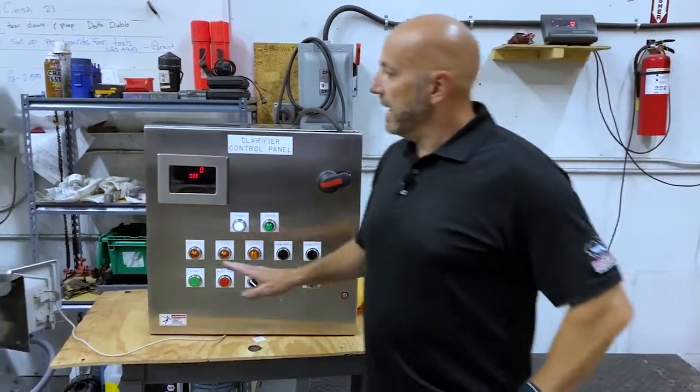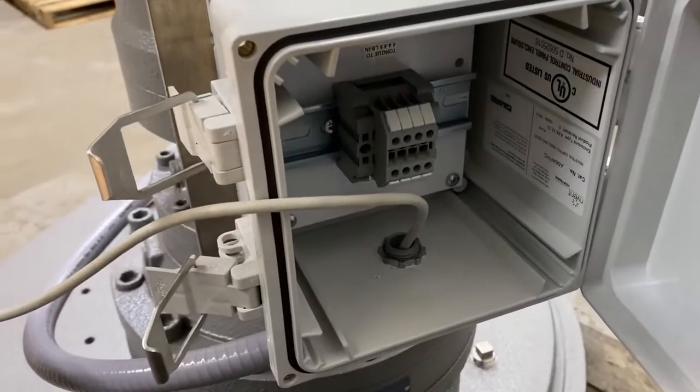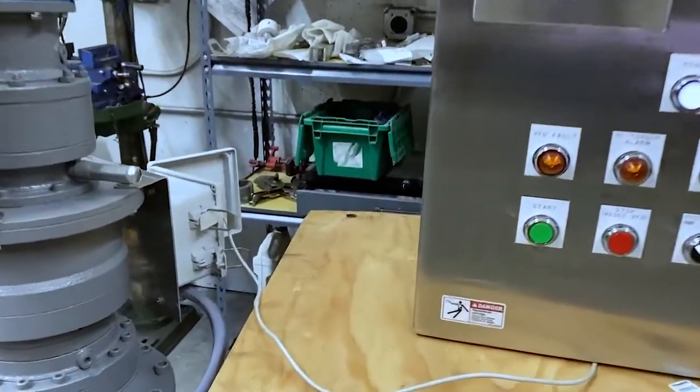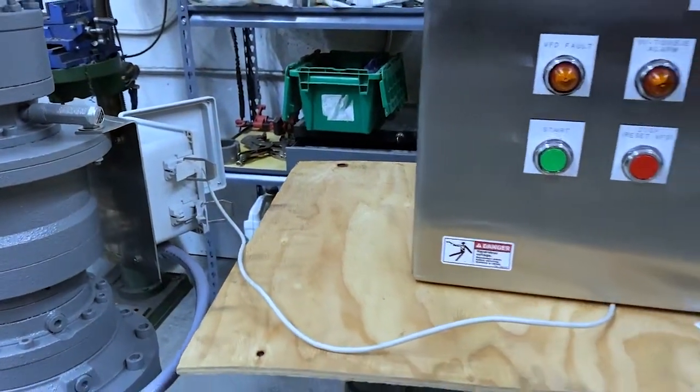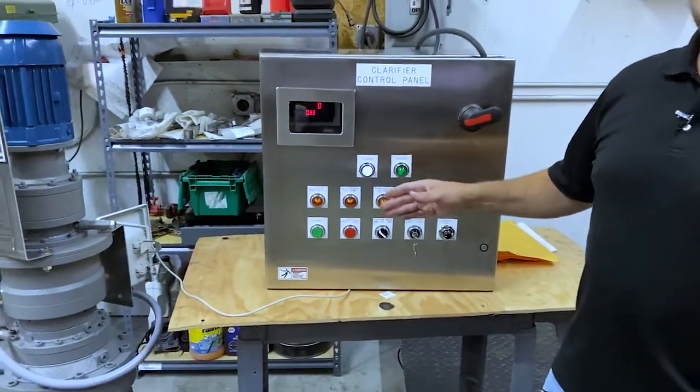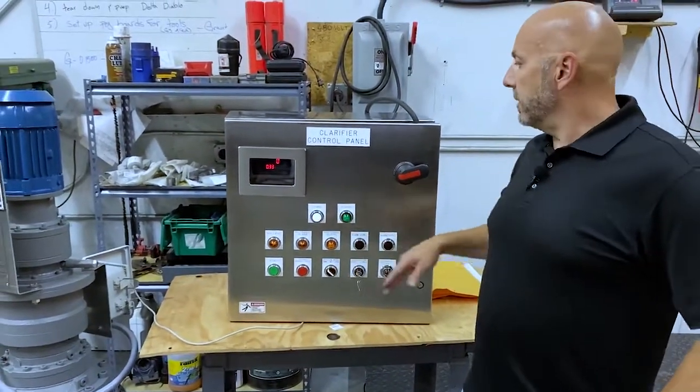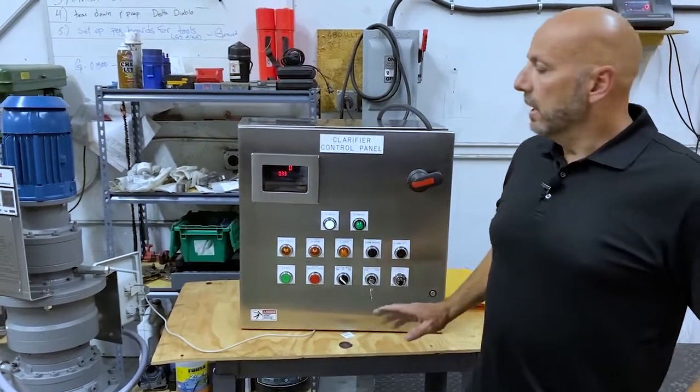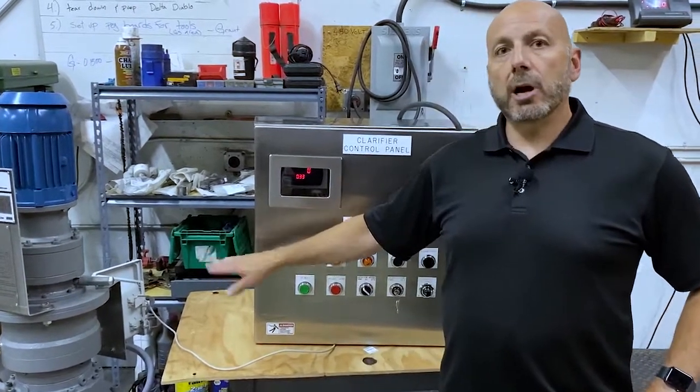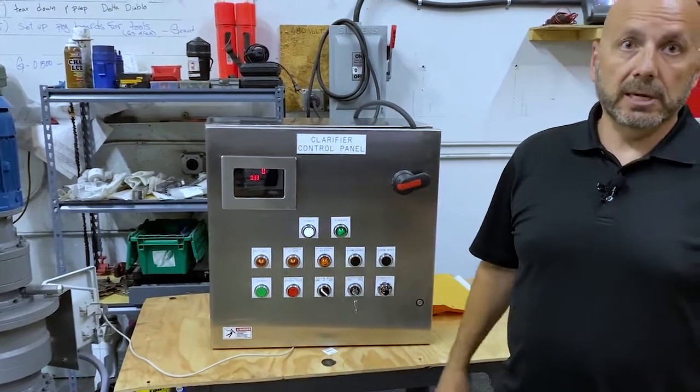There is a junction box on the back of the drive unit that the cable you're seeing out front is typically wired to. This cable does have a shield wire that will be landed to a terminal inside that box. That shield wire needs to be grounded all the way back to the panel. We highly suggest that the cabling you use from the J-box on the drive back to the panel is a shielded cable.